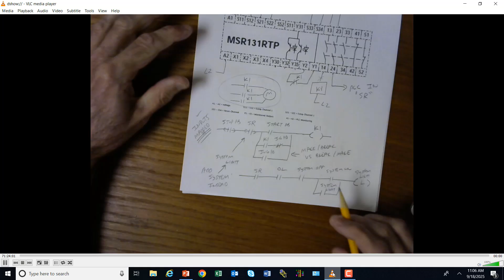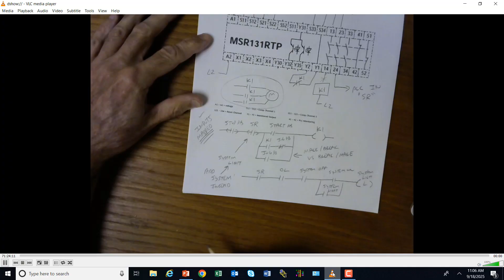And then the other thing you could do, you just could take the safety relay here and add a system light instead. So instead of making this the safety relay, you would make this the system light, okay? And then the system light would consist of the safety relay, which would be closed. And now we're adding the overloads in here because it asked to be monitoring that as well. The overloads are closed.